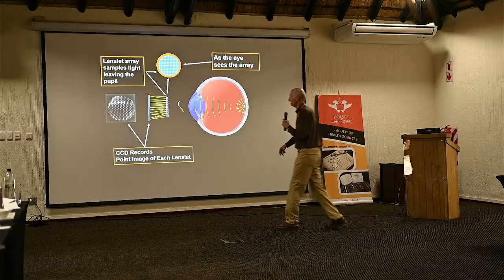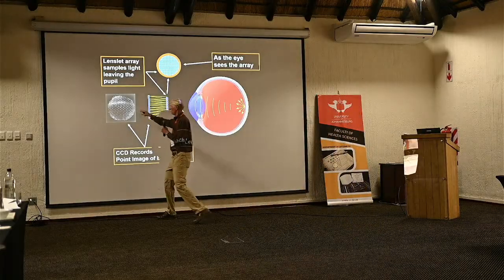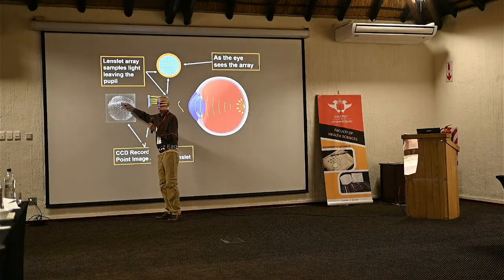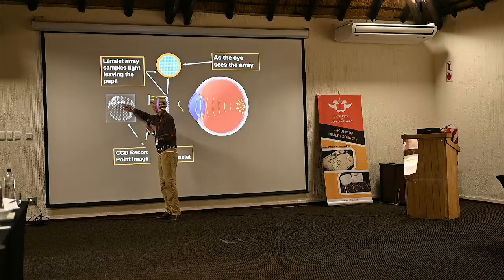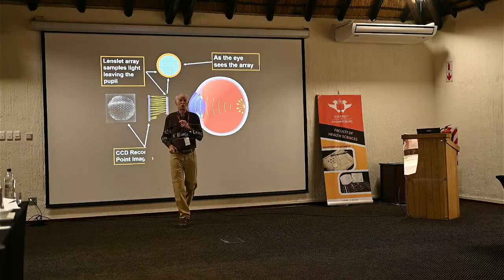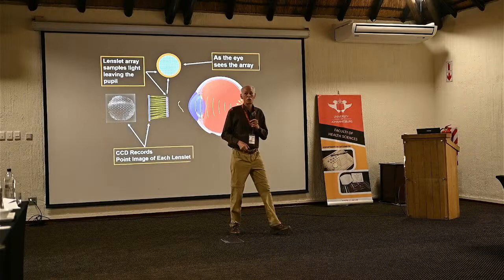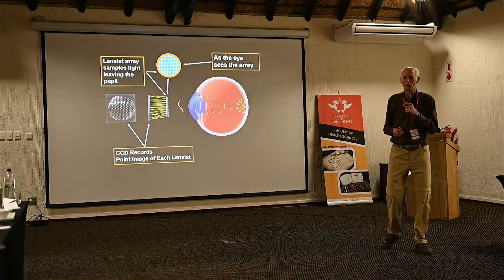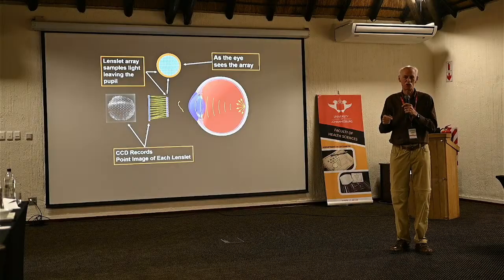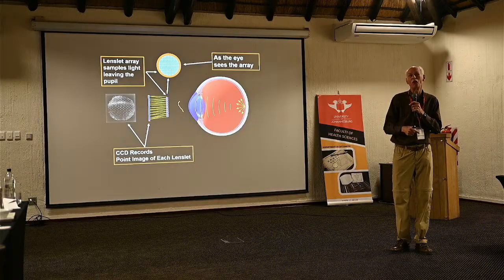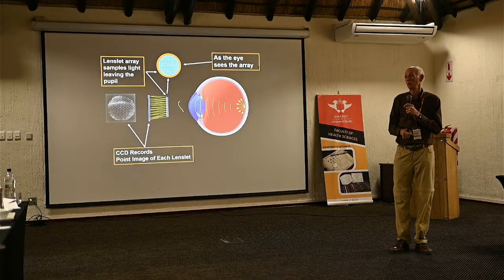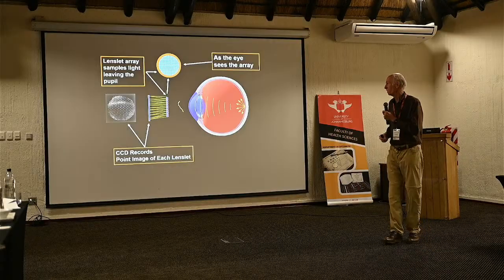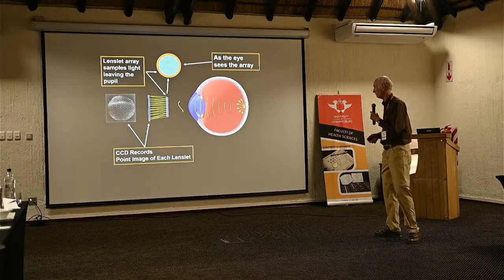And by golly, some of these spots are really crammed together, really close together, and maybe you're not quite sure which lenslet produced which spot. So one of the techniques that the instrument manufacturers use, they put what's called a range limiting aperture. It prevents spots moving too far. So it's got a limited dynamic range for that reason, but at least it doesn't get confused.